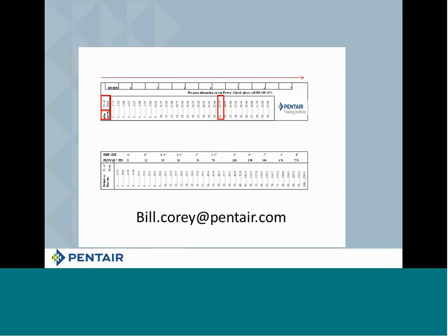You take the ruler and say, with a dumb vacuum gauge, you're only 2 feet off the water. But the vacuum gauge is saying, yes, that's true, but I'm doing so much work that it feels like 24. That's how hard the pump has to work. Now remember, the deeper I go to water, the less water I get. So what it's telling me is the pump is having a hard time getting water to it.